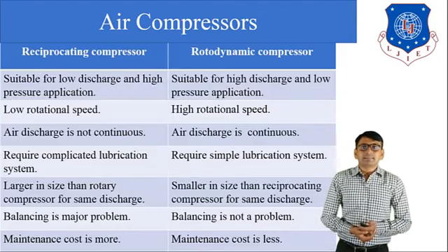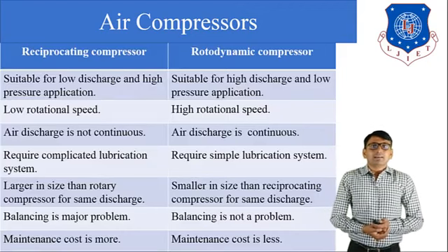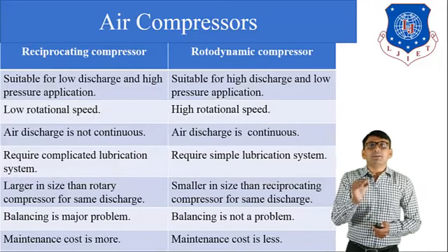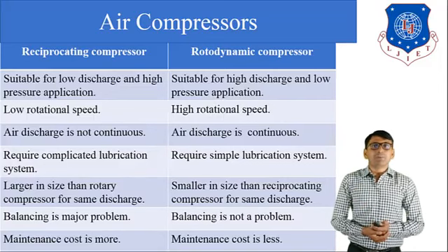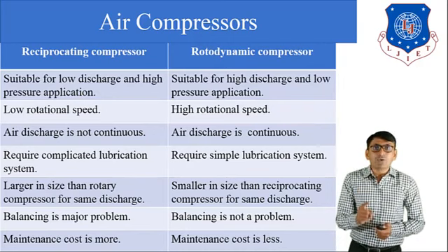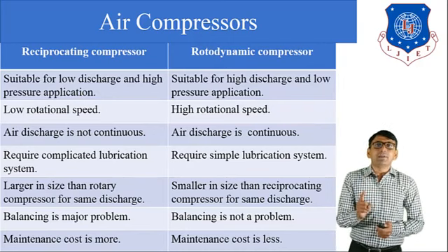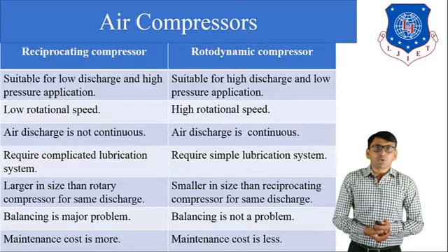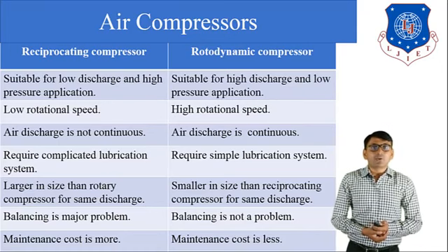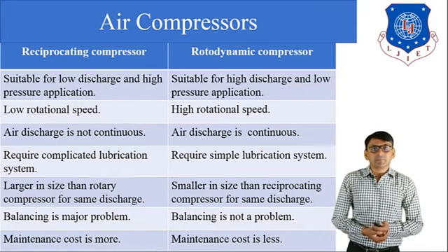Then we discuss, at last, the comparison between reciprocating and rotodynamic compressors. First comparison: the reciprocating compressor is suitable for low discharge and high pressure applications, and the rotodynamic is suitable for high discharge and low pressure applications. Second comparison: reciprocating has low rotational speed, and rotodynamic has high rotational speed.